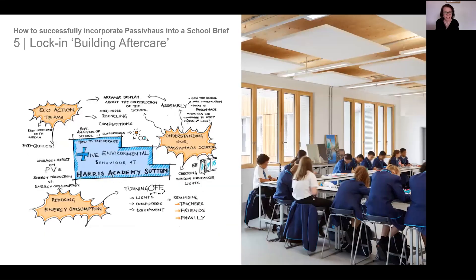A building aftercare framework provides wider benefits - it provides an opportunity to learn more about the strengths and weaknesses of a building and its occupants, and gives everyone - the client team, design team, and contractors - an opportunity to reflect on lessons learned that can be applied to future projects. There was a similar story at Architype's Enterprise Centre at UEA, where monitoring data showed a gradual increase in energy consumption as the building started to get used more - actually a lot more than predicted, because it was perceived to be such a popular working environment. Despite the substantial increase in occupancy, it's still meeting an A rating in the DEC. This influx will naturally mean adjustments are needed to the MEP system, so it's important that there is a structure in place to keep monitoring and checking that the building is operating efficiently.